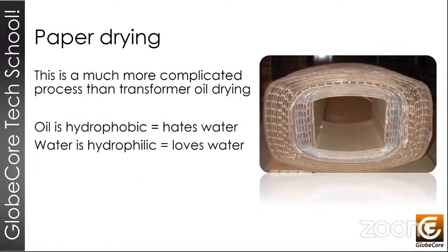The important thing to consider here is that there are inherent characteristics of oil and paper that influence this, and this is the fact that oil is hydrophobic, which means that it basically hates water, and paper is hydrophilic, which means it loves water. This means that the water can and will easily transition from oil to paper. That's why we always hear that 97 or 98% of water in a transformer is concentrated in paper, and that's actually true. So the paper drying processes have to be planned in advance, because in many cases it requires taking transformers out of service entirely and sending them to the factory or to a specialized workshop for maintenance. Next, please.